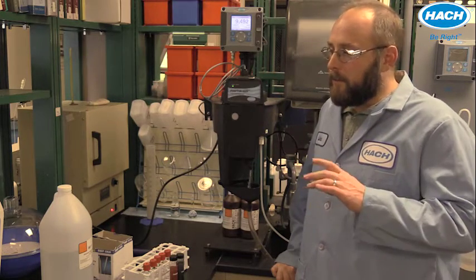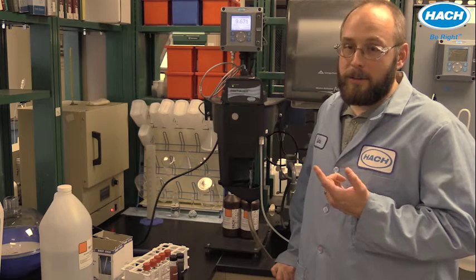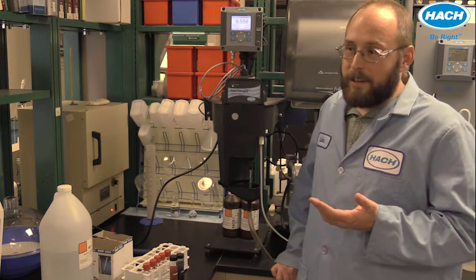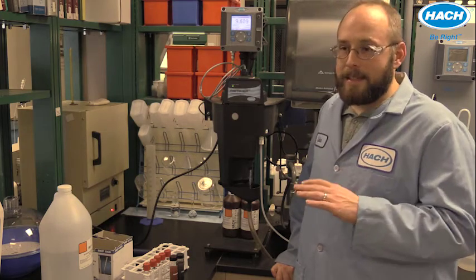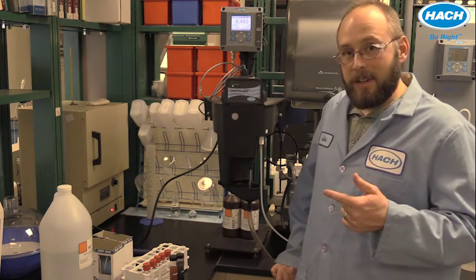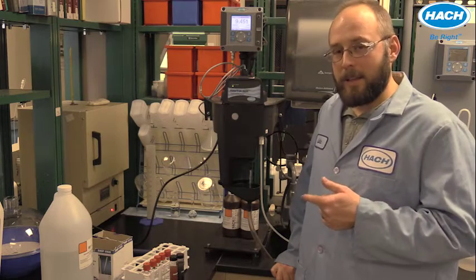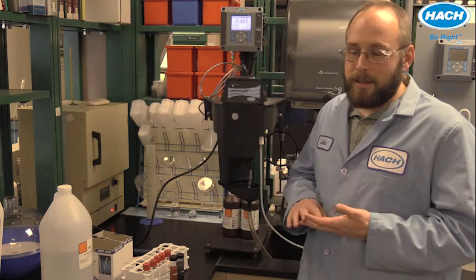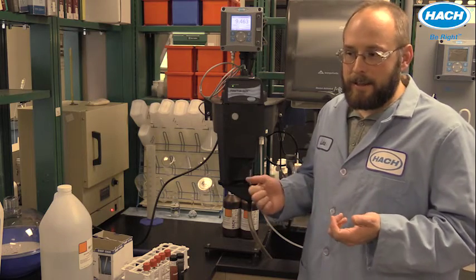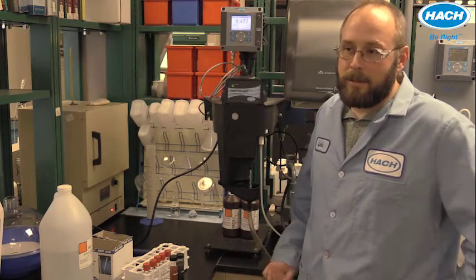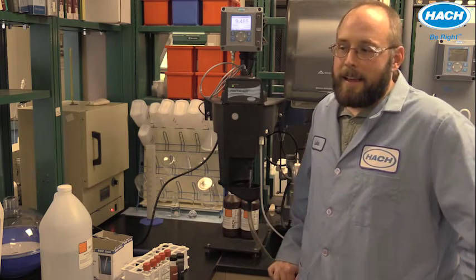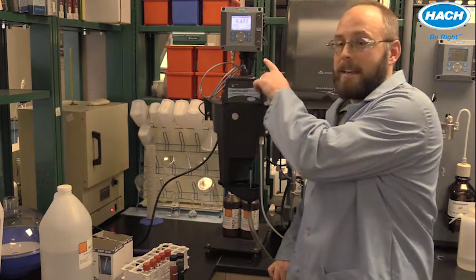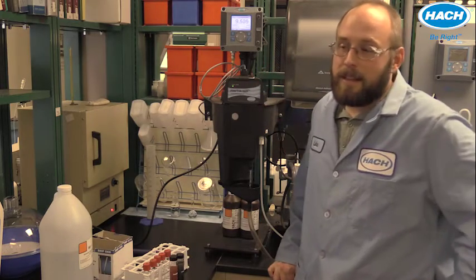So what I'm going to show you now is how you can do that, how you take the sample, which is not very difficult. And once we take the sample, in the next video I'll show you how to analyze that sample with the lab method. And then once you have that data, you can plug that into a simple linear equation, which is outlined in the calibration guide available on the Hach.com website, and that will calibrate milli-NTUs to parts per billion iron.